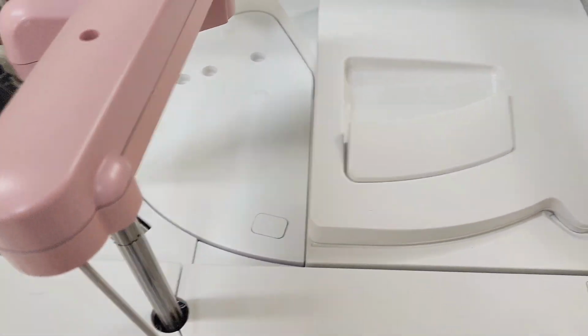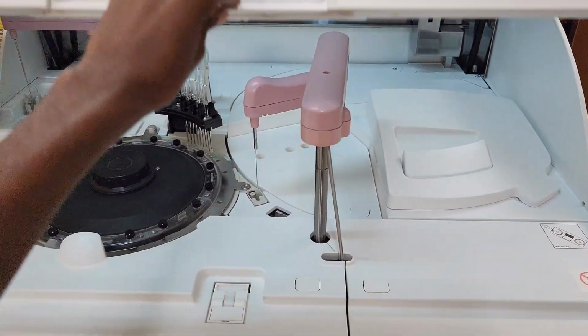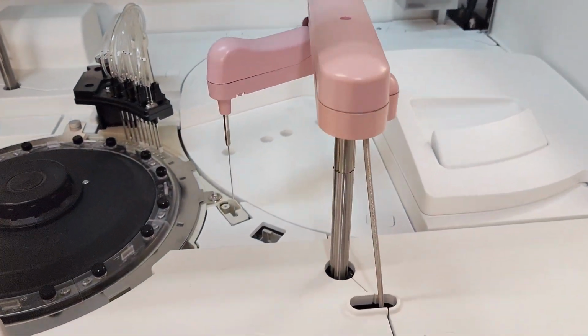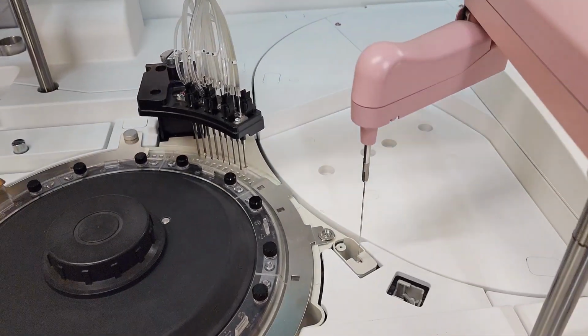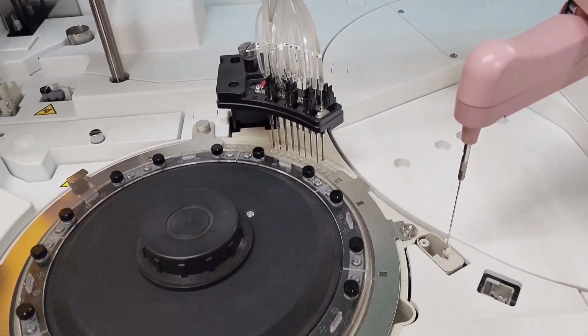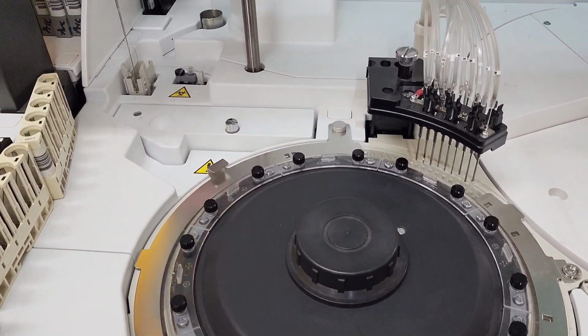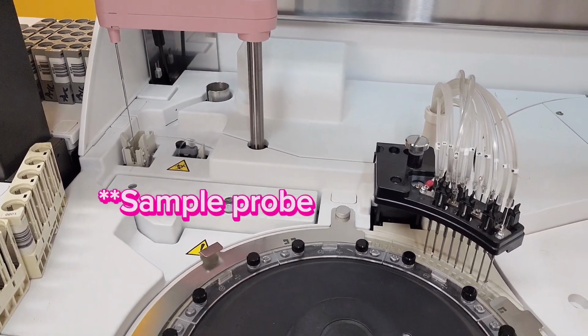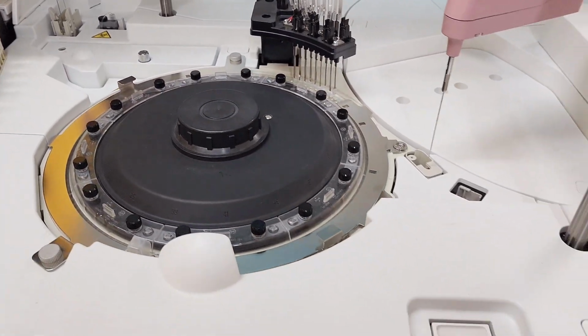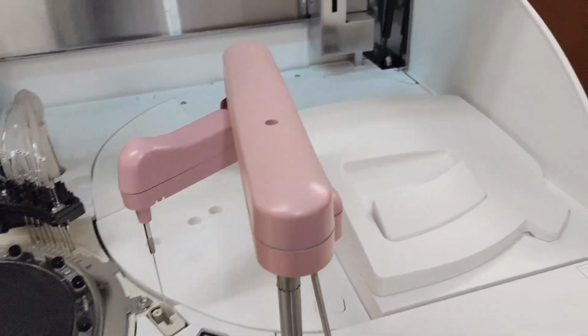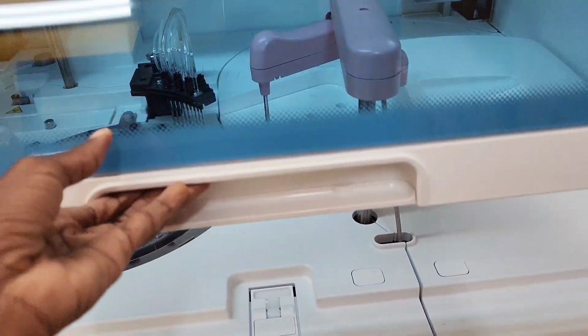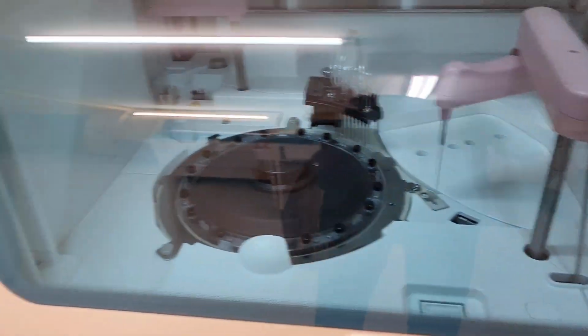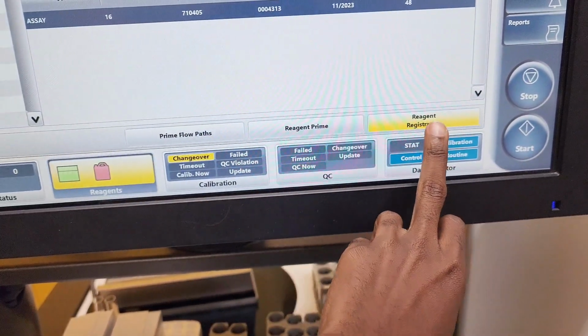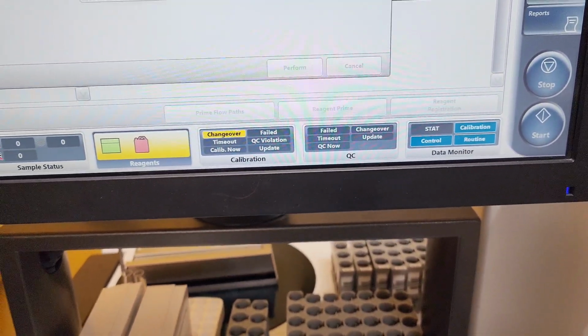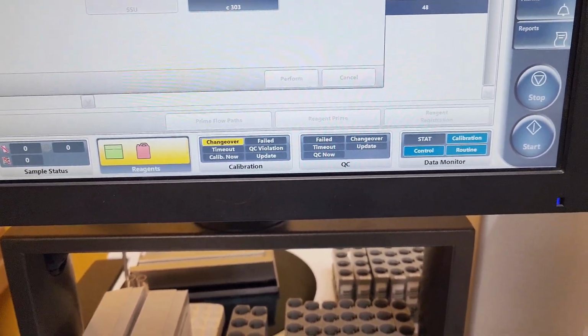So yeah, that's that. Here we have the reagent probe and the sample probe. This one that I'm focused on here is the reagent probe, and then the one on the far left, that's the sample probe. That is the probe that would take up the sample and place it in the wells. The black thing that you're seeing there, that's where the wells are for mixing of the reagent with the sample. Once we add a new reagent to the machine, we have to register that specific reagent. So that's what I'm doing now.